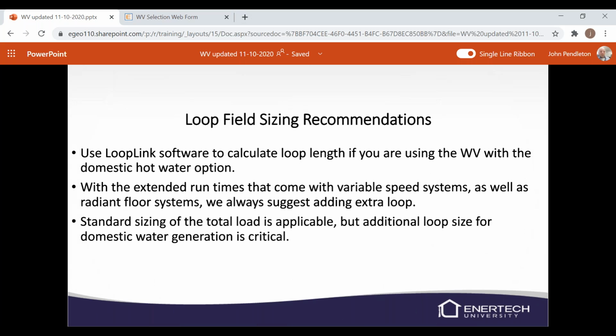Loop field sizing, we would recommend using the Loop Link software to calculate your loop length. If you're using the domestic hot water option, you may need a little bit of extra loop because we do have extended run times that come with the variable speed. So we do suggest adding extra loop. If you got any questions on that, give us a call and we'll have you talk to the people in design and they'll give you their take on that. Standard sizing of the total load is applicable, but you may want to add more loop for the domestic hot water.